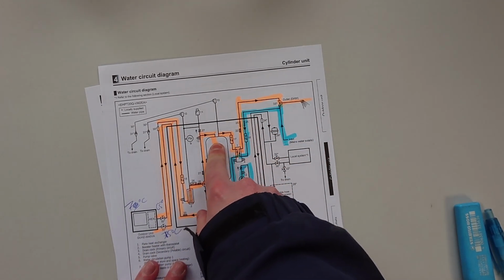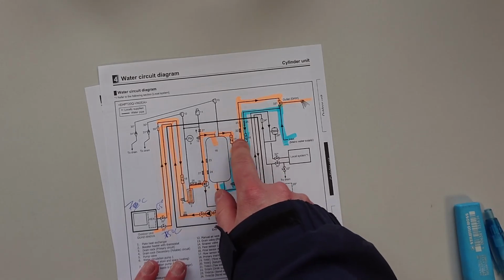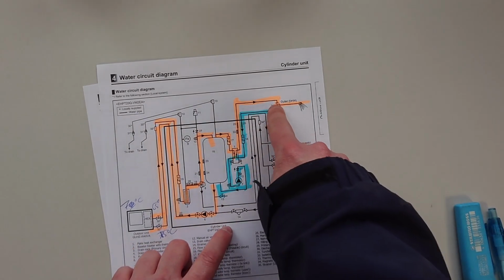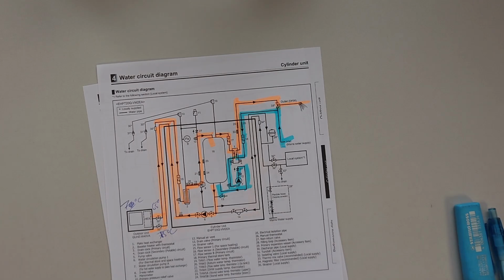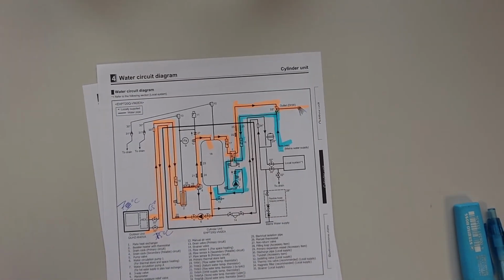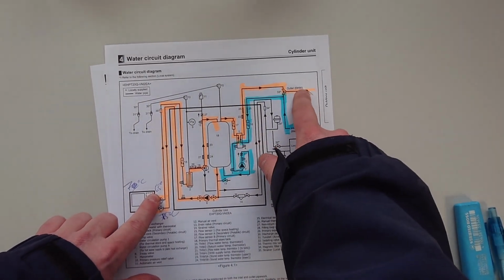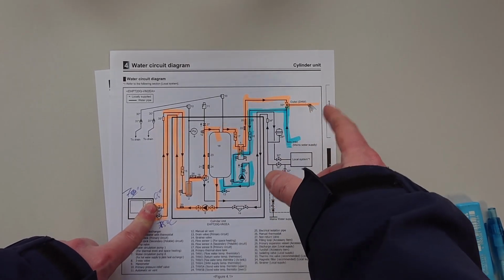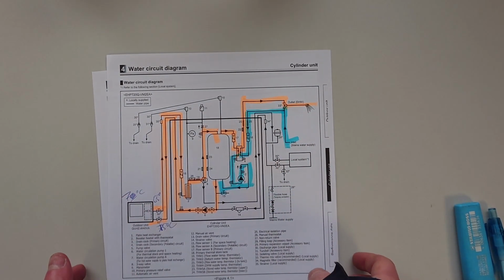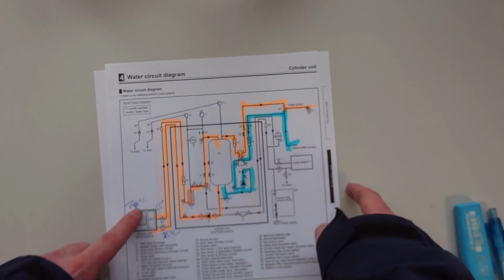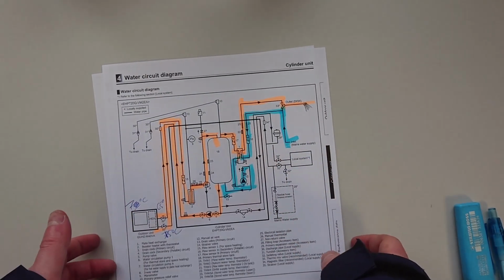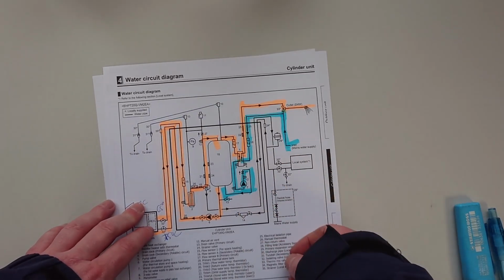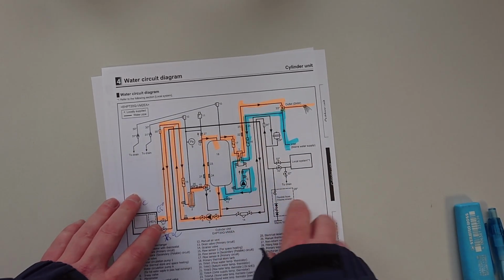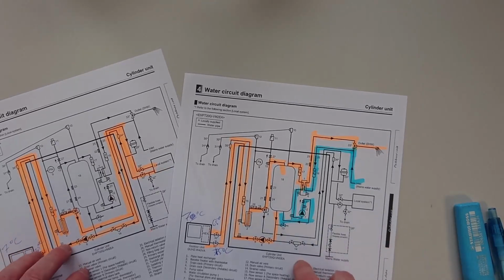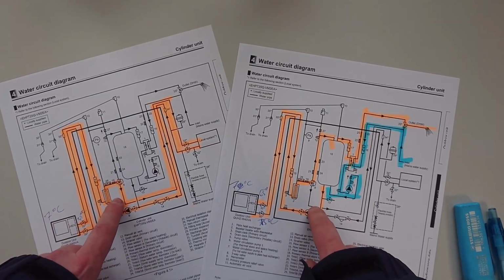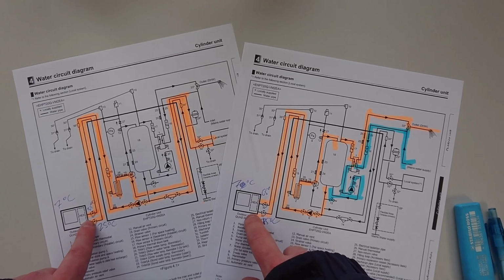And now you've got the hot water from your heat pump that then gets circulated back around through this heat exchanger, which then keeps the temperature up on the water that goes into your house, or into your shower and your hot water. And it does this at much higher temperature because you want this higher, because there's a limit to how much flow you're going to get coming out of your shower and your hot taps, which it turns out is less, and you want it a lot higher than you do for covering your body with. So that is, quickly, well, it's not quick, but that is quite simply how the heating and the hot water system work, just from the water flow side of the system, mostly ignoring how the actual physical heat pump system works.